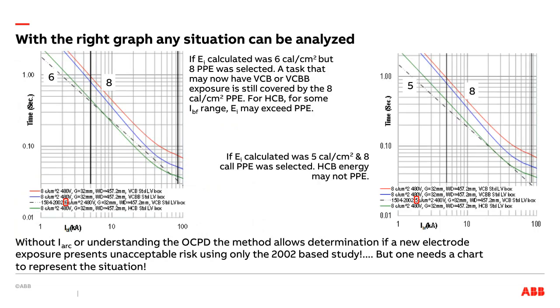And my suggestion is you can do an analysis. If you calculated 5, you draw your energy boundary at 5 based on the old study method. You would draw the boundary at 8, because that's the PPE you have, based on the new study method. As long as the black line is not above the green line, 8 calories is enough. It will cover you. Now, you may want some margin, because that's your policy. Then put a 4 here. That line will shift a little bit, and you may not be able to use the 8 for every situation.